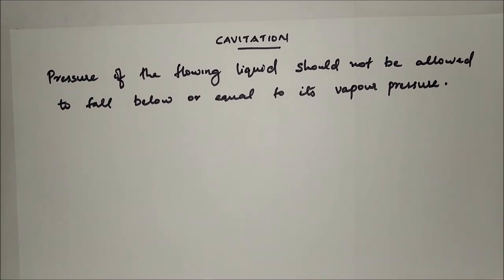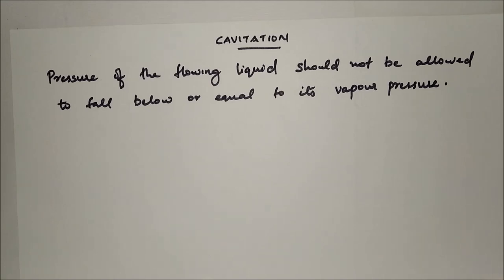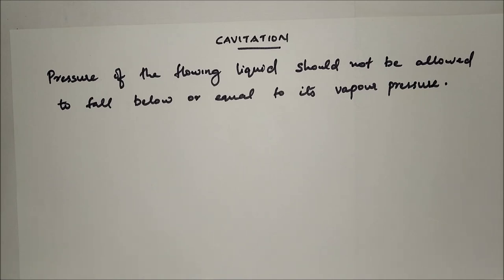The effects of cavitation are: the metallic surfaces are damaged and cavities are formed on the surfaces. Due to sudden collapse of vapor bubbles, considerable noise and vibrations are produced. The efficiency of the turbine decreases due to cavitation because the force exerted by water on the turbine blade decreases, and the work done by water or output horsepower becomes less, hence efficiency decreases. The hydraulic machines subjected to cavitation are reaction turbines and centrifugal pumps.